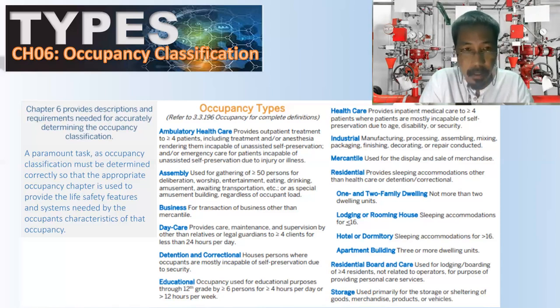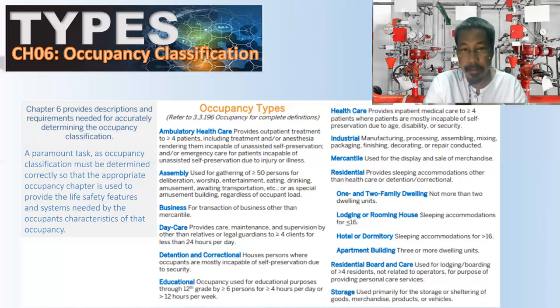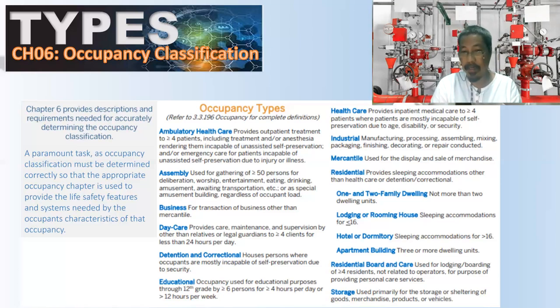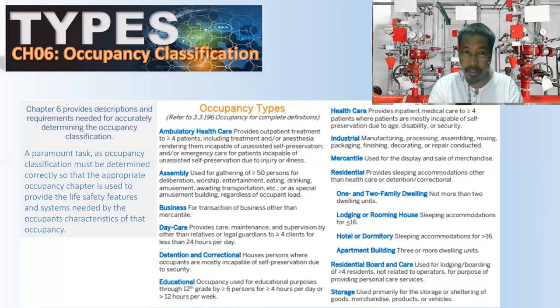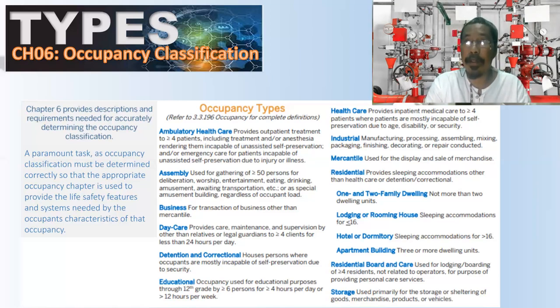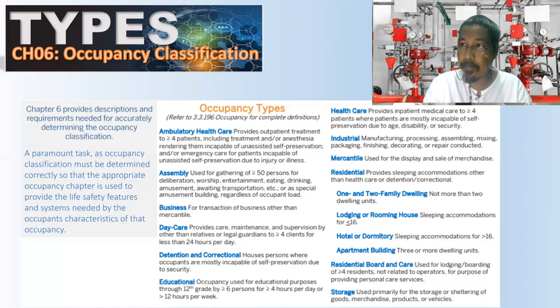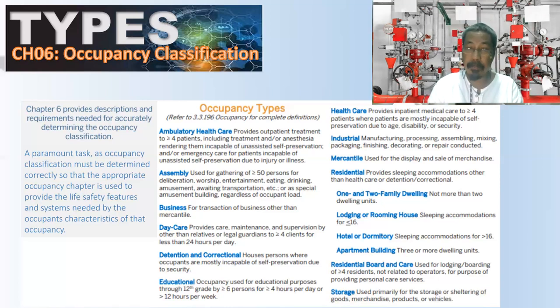Eating and drinking establishments such as restaurants with 50 or more persons are classified as assembly. Amusement venues like a gaming cafe with 50 or more gamers are also assembly. Additionally, awaiting transportation — such as terminals where 50 or more persons are waiting for a bus — also qualifies as an area of assembly.